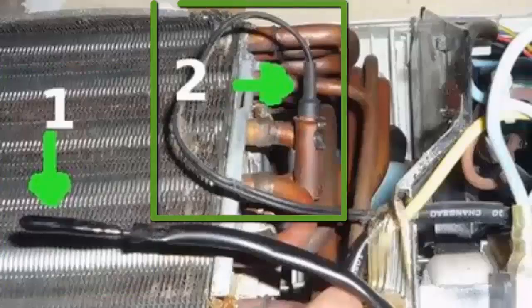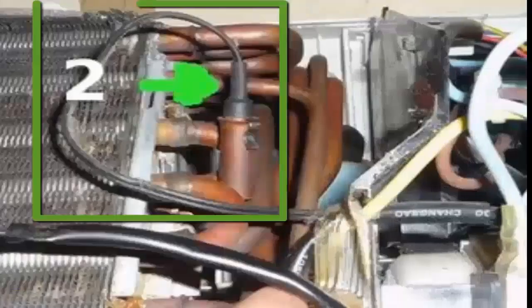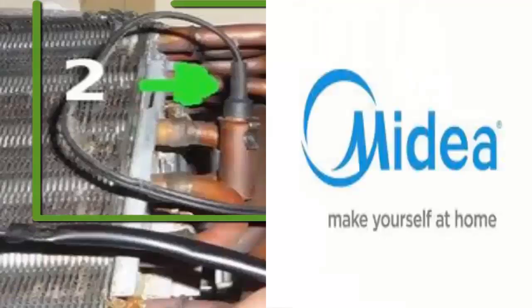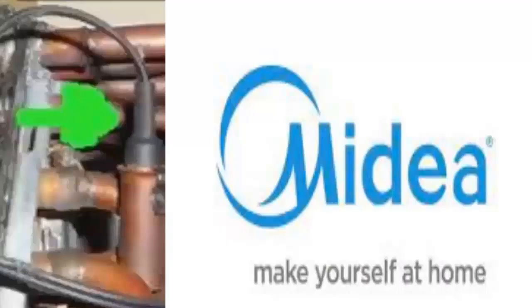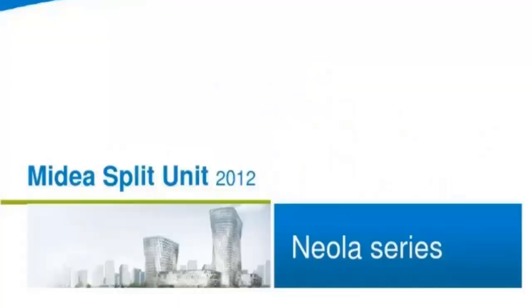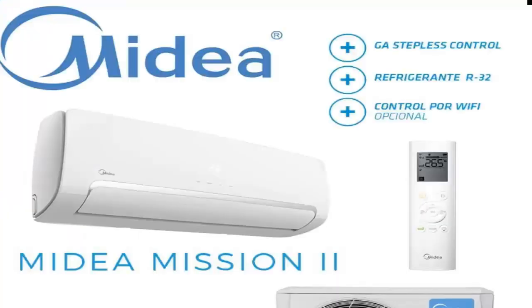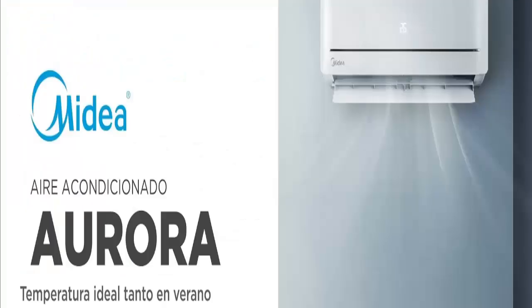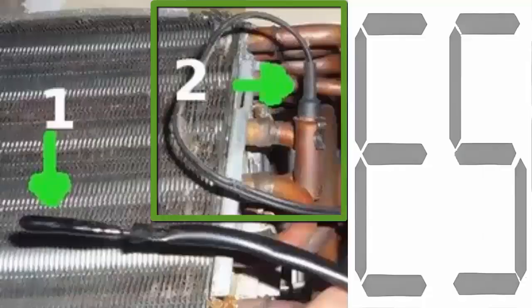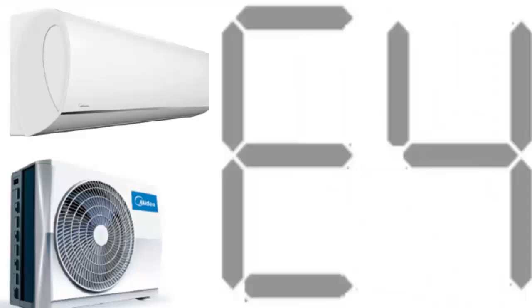2. Coil sensor. The coil sensor measures the direct temperature of the evaporator to determine if there is freezing in the coil. An error code is generated when the sensor sends abnormal signal values, either due to an open circuit or a short circuit. For fixed-speed non-inverter MIDEA models from the Neola, Mission, and Aurora series, problems with this sensor are identified with the code E5, while in Blanc models, they are identified with the error E4.